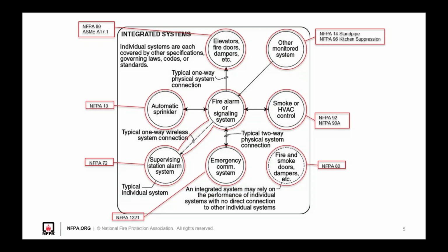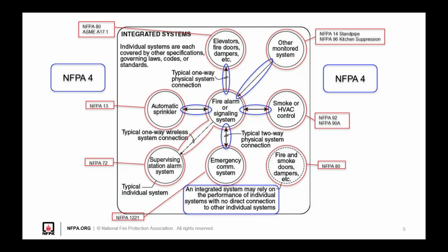So a test of the fire alarm might make sure that given a signal from the relay, the fire alarm produces the correct response. And then a test from the kitchen hood might make sure that a signal is sent from the kitchen hood to the relay. But then there's questions about, well, what about testing to make sure that relay works? And if the connections inside the relays are working, make sure that the response from the fire alarm is as intended. What about if the communications between that kitchen suppression hood and the fire alarm are maybe not through a relay? Maybe it's through something like a data connection or a wireless interface. How do we know that all these communications are working correctly? And all these questions get answered by NFPA 4.